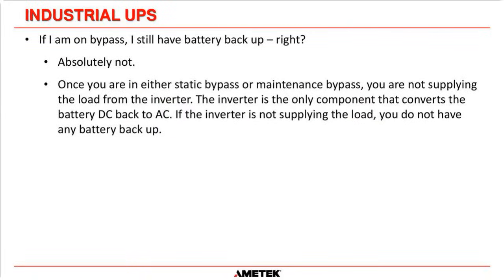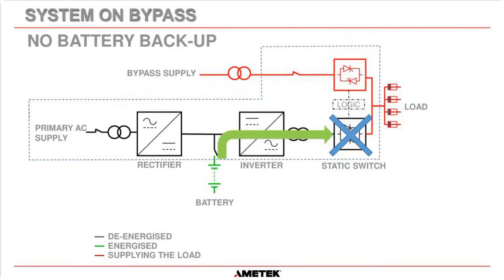More questions. If I'm on bypass, I still have battery backup, right? Absolutely not. Another really big misconception. Once you are in either static bypass, in other words, on bypass through the static switch, or you are on maintenance bypass, you are not supplying the load from the inverter. And if the inverter is out of the game, then you do not have battery backup. Simple as that. You only have battery backup when you are on inverter. So that is a very big misconception. And there's a picture showing you it, okay? If you are on bypass, that means that static switch is off, and therefore you have no way of getting the battery power through the inverter and out through the static switch.